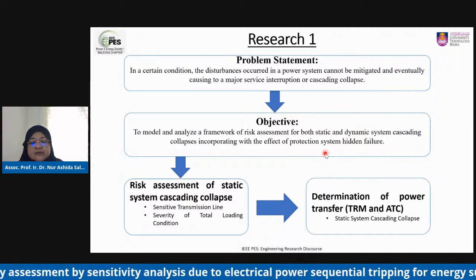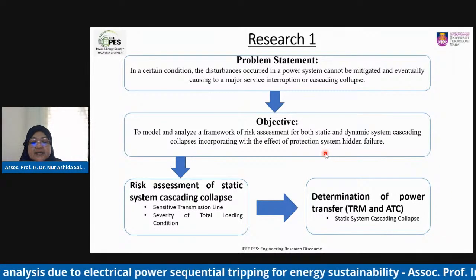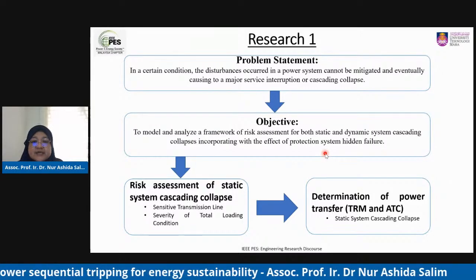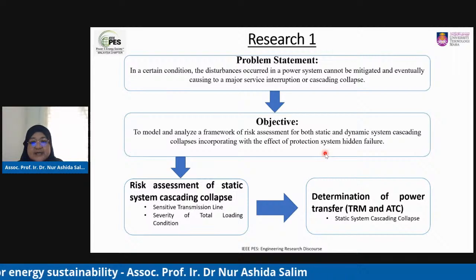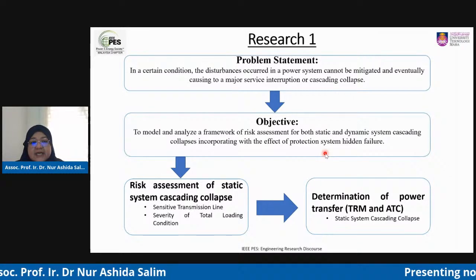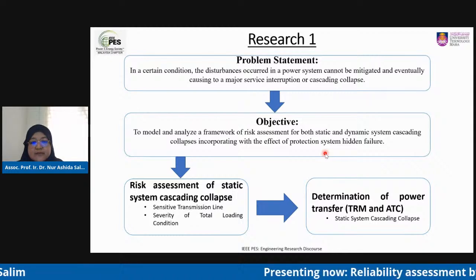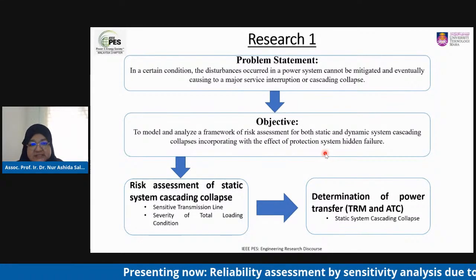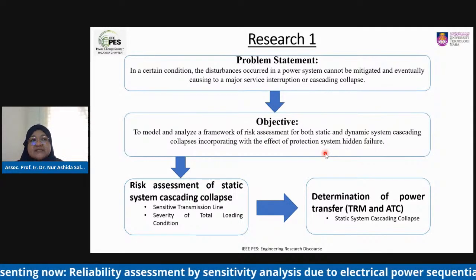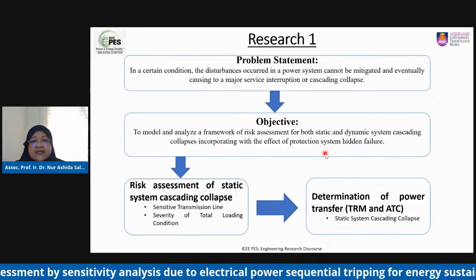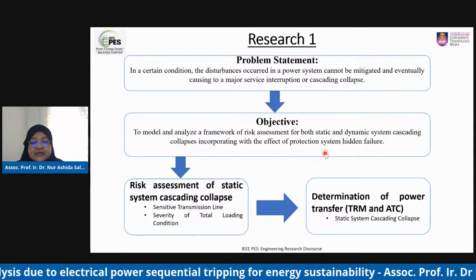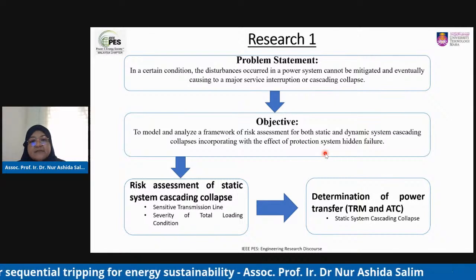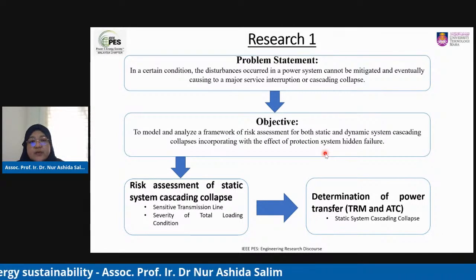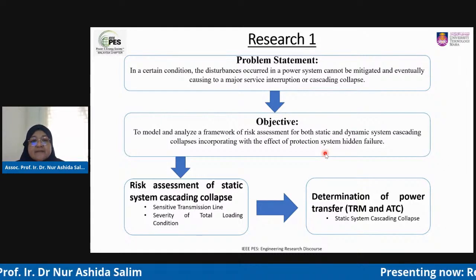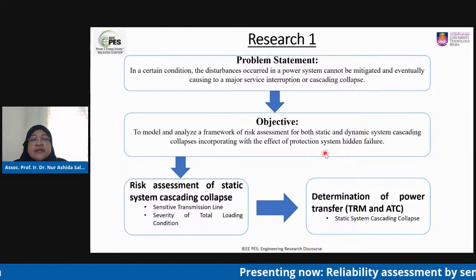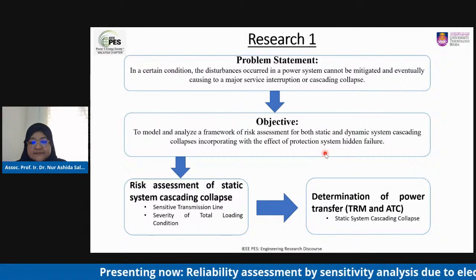From that, I also calculated or modeled to find the available power transfer due to this cascading collapse. As I mentioned, the cascading collapse can be stopped by two conditions: either the whole system collapses, meaning no more power transfer, which is total blackout, or there is no more exposed line or exposed generator tripping, meaning parts of the system can still supply power. So we want to know the amount of power that can be transferred within what we call partial collapse.